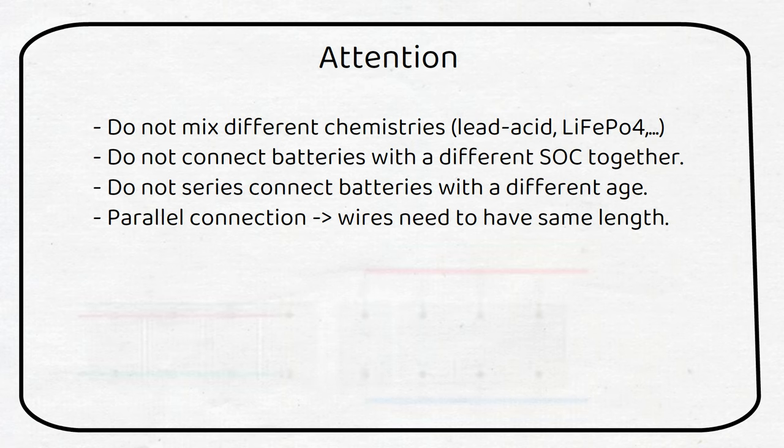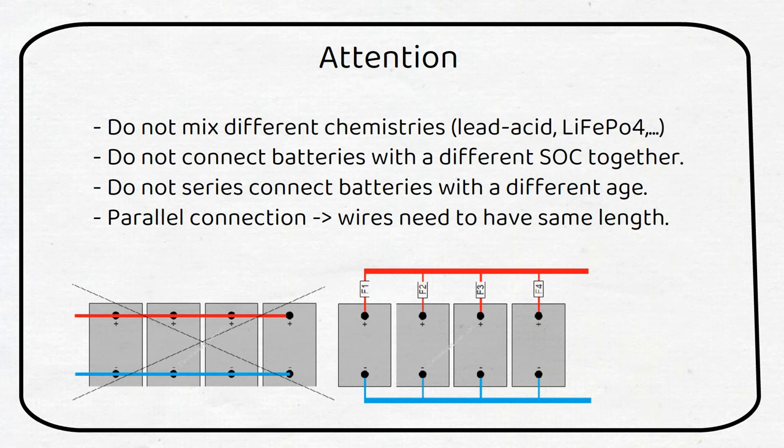When connecting two or more batteries in parallel, make sure the wires are the same length. Otherwise one battery will work more than the other. We can solve this by installing a bus bar and having every wire going to the bus bar the same length.